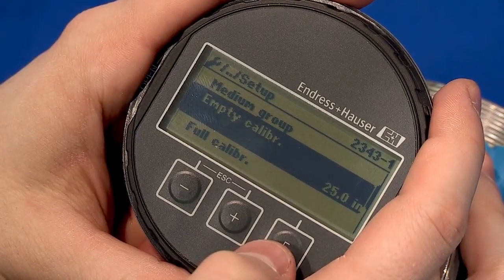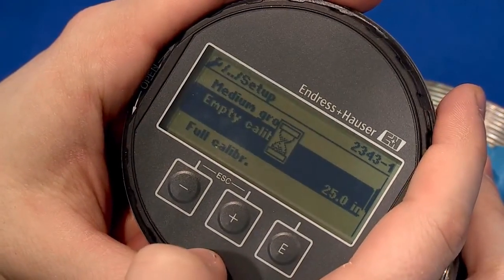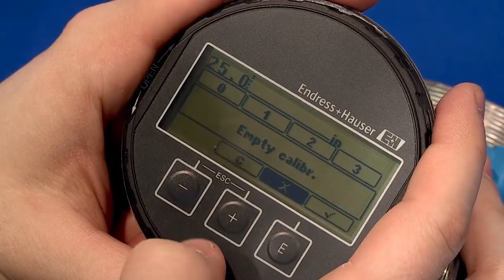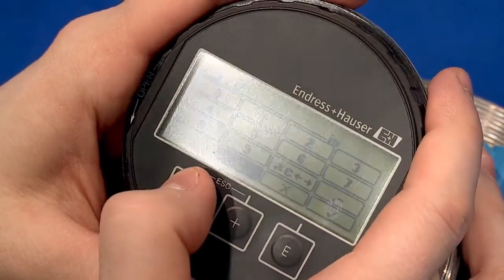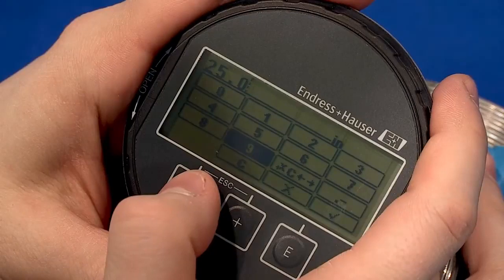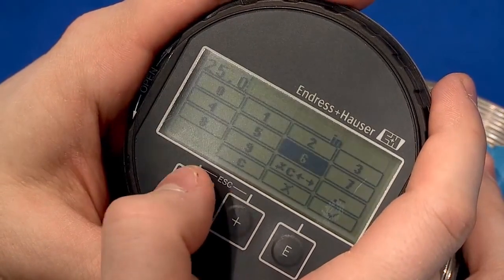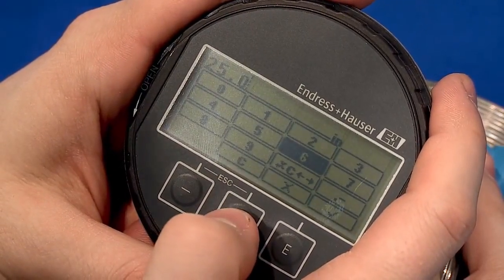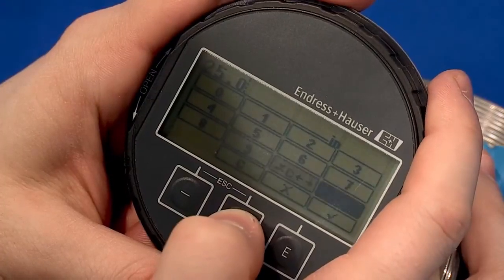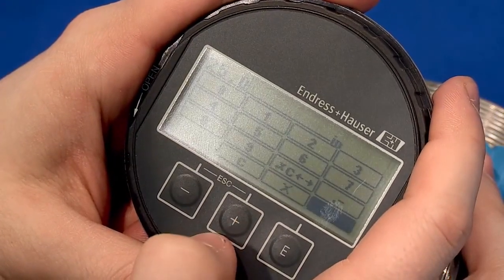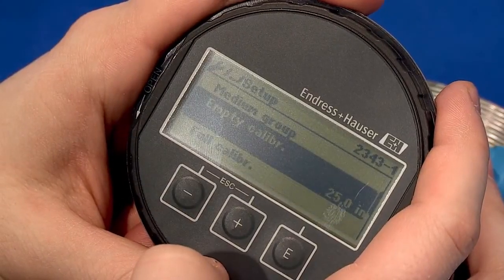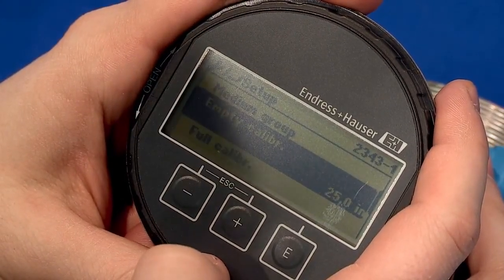Once you press Enter to enter into the parameter, a keypad of numbers will appear. Use the plus and minus buttons to scroll through the numbers, changing one digit at a time. Once the correct number has been entered, scroll through to the check mark and press Enter to confirm. We will set our empty calibration to 25 inches.